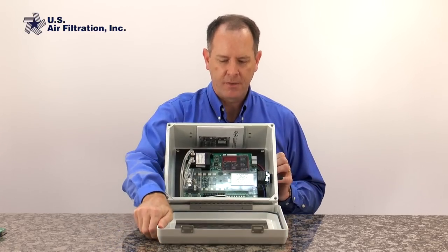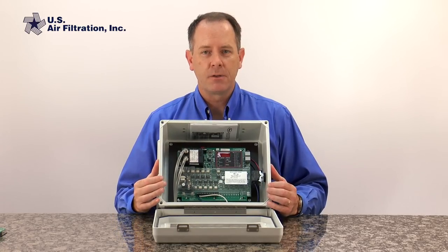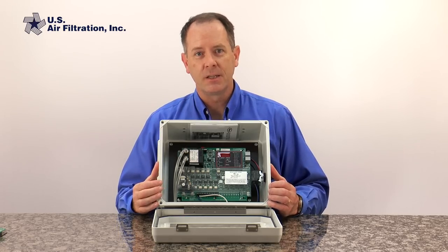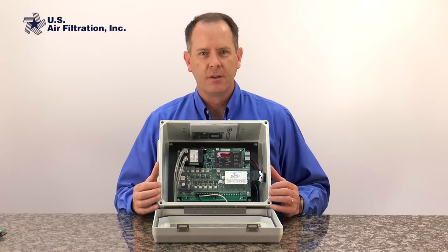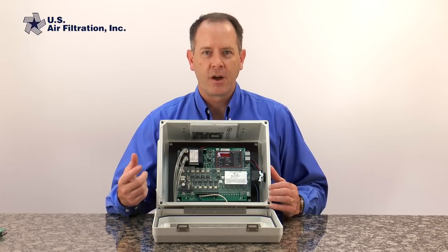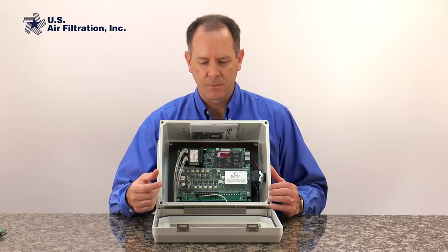I have here a control panel that has a different kind of timer board in it that will allow us to do this on-demand cleaning. This timer board has Photohelic capabilities — that's a term for a device that will basically turn on and off the timer board based on the differential pressure readings it's getting from the dust collector.